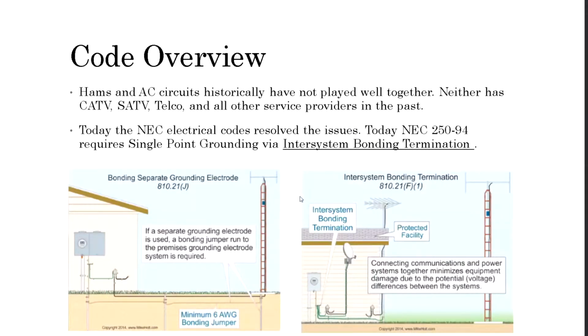Okay, traditionally, hams and AC circuits haven't played well together. Neither has cable or satellite or telephone interface, up until the mid-'80s when they finally got their act together. But us hams have kind of lagged behind. Today, NEC electrical codes resolve most of the issues with 250.94, which requires single-point grounding via the intersystem bonding termination. Earlier in the doc, when we started today, I gave you some references. One was Mike Holt's code forum, and he's got several white papers, one on Article 810, which is strictly dedicated to amateur and CB radio operators. And they're showing basically the single point, how it's done.